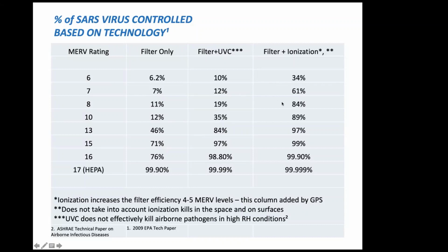But what's interesting is we have a MERV-8 filter. You're now 84% because of that agglomeration feature of the technology. We're increasing the filtration efficiency of the system, and we're treating these contaminants out in the space. A MERV-13 filter is looking more like 97%, and it just becomes even more efficient above that.